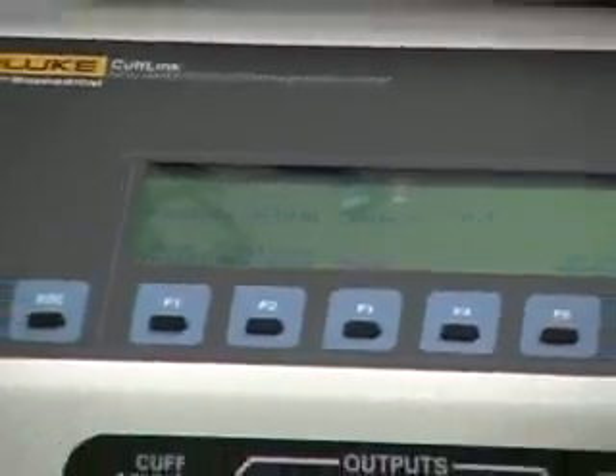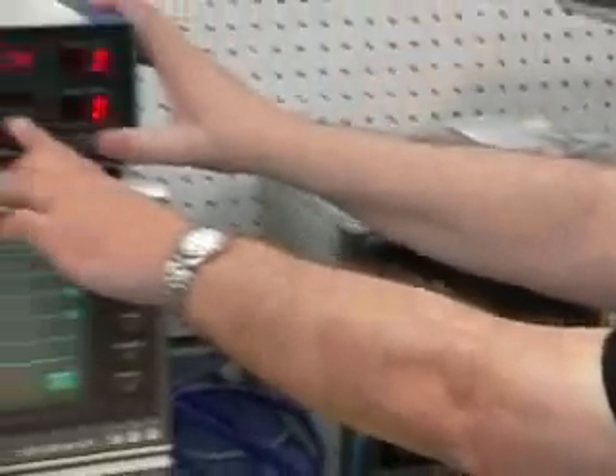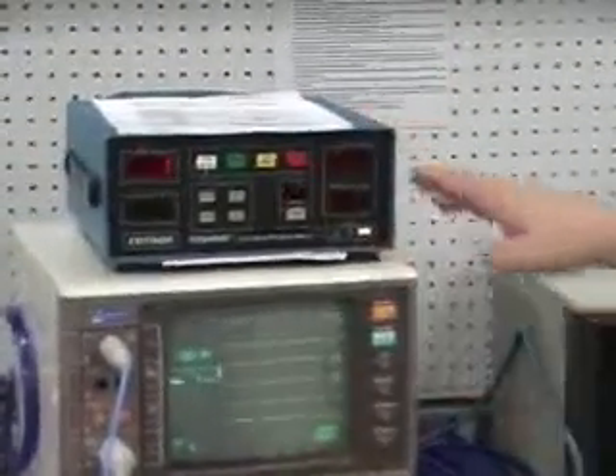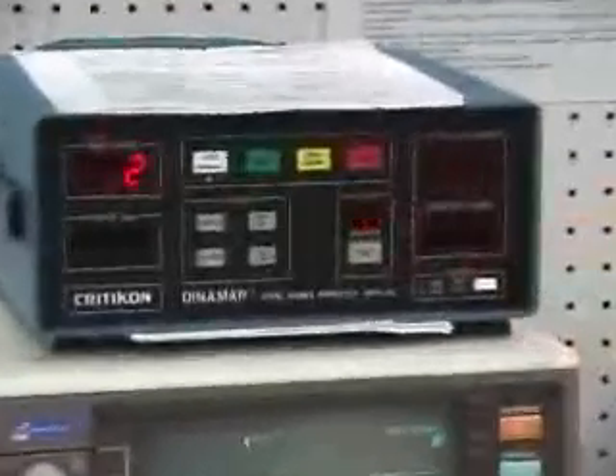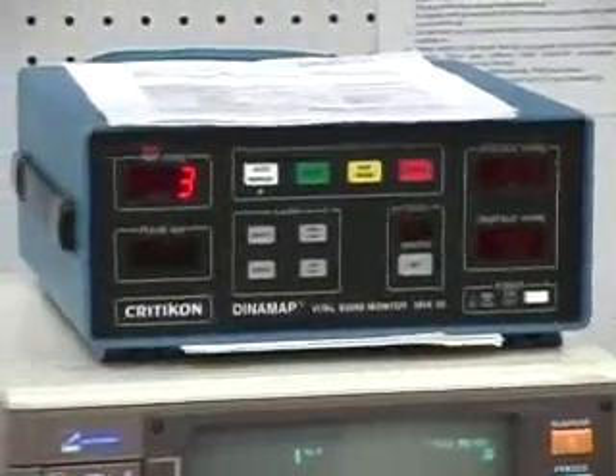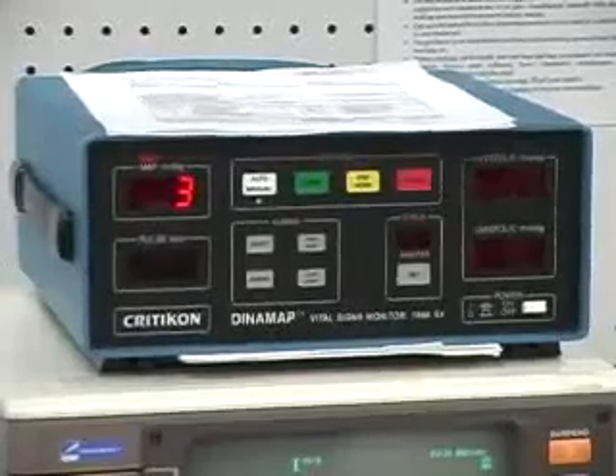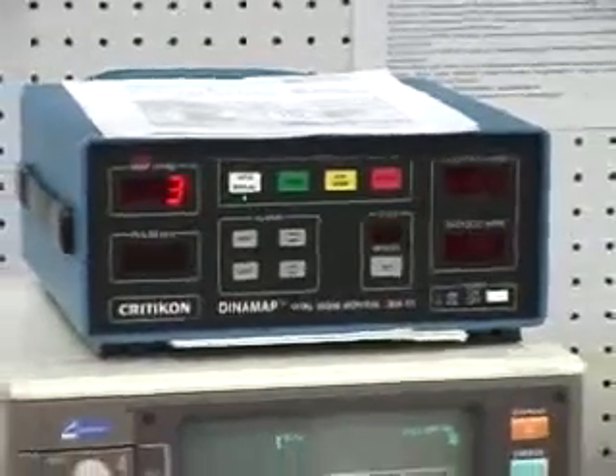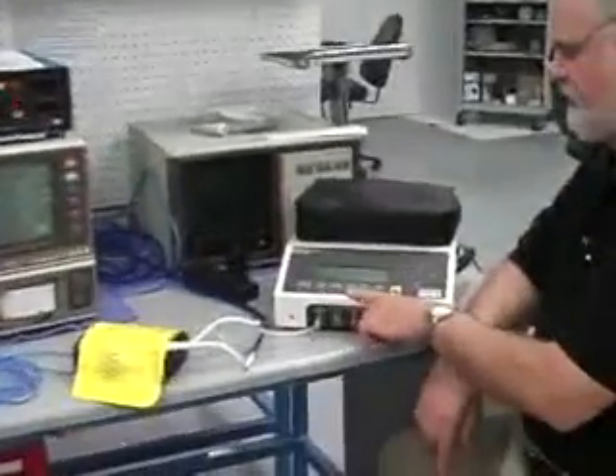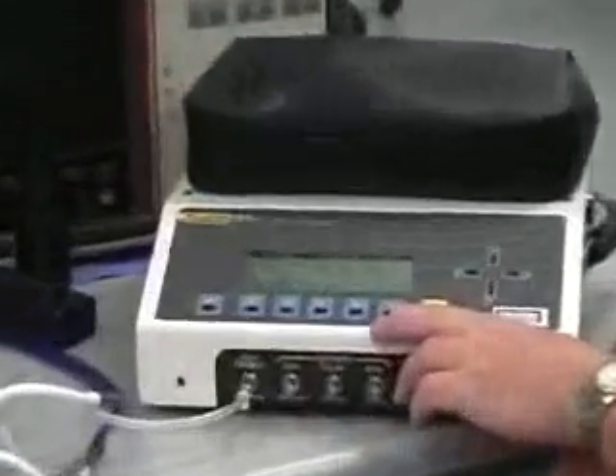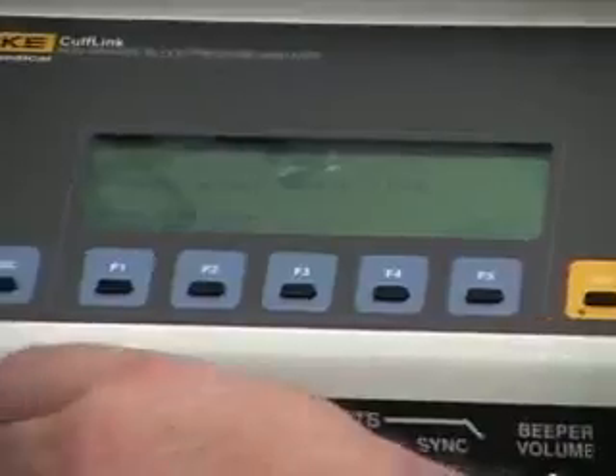And now with this system fully set up, attached with a cuff, we can then put the Dinamap in a diagnostic mode by holding the minutes down and then the power and letting it go, and that will now make your cuff pressure or your mean arterial display read basically a manometer pressure. So with the Cufflink you can turn the pump on, turn it off, release the pressure, print the data, and also zero the transducer. And if you want, you can just simply unplug this, vent it to atmosphere.